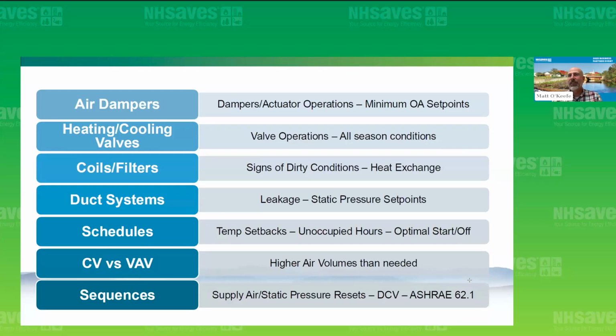There's a lot that folks will look at from a commissioning perspective, but for air handlers, you're checking things like damper operations to see if they're modulating as expected with the building management system, and that the outside air damper is at a minimum as much as possible. The same goes for heating and cooling valves. If you find them stuck in a certain position, they're just using more energy than they need to. But you also want to make sure, since heating and cooling valves are sometimes shared, to test them in both seasonal conditions, so they operate as they should in heating as well as in cooling seasons.